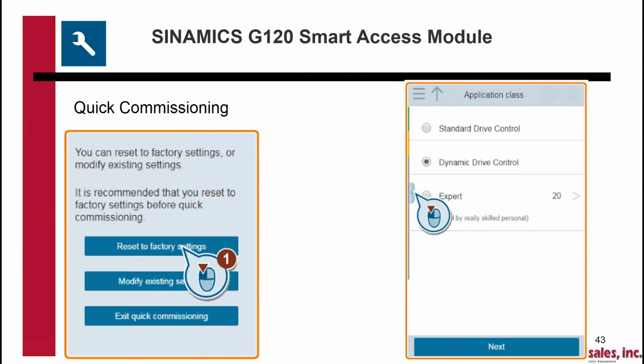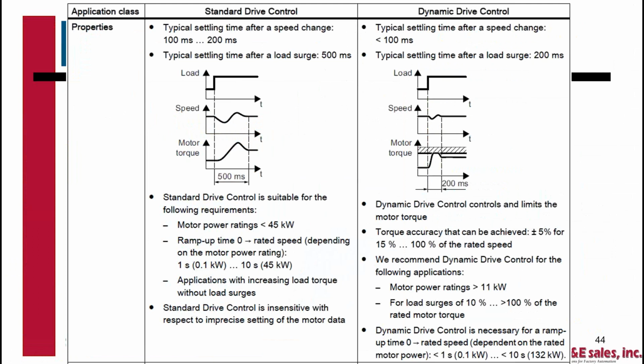If we say reset, it'll go through the reset process. Then it's going to pop up your application class. Again, this is slightly different from the V20, with more options. You've got standard drive control, dynamic drive control, or expert, where you can select some different parameters. Standard drive control has very little torque control and is not tightly speed regulated, for ramp up times greater than 1 second. Dynamic is more vector control, so you tighten up your speed loop. You can do some torque limiting and get a little better torque control with dynamic.